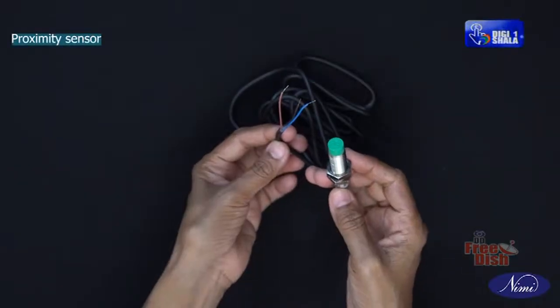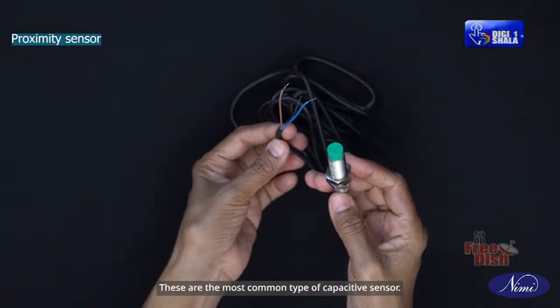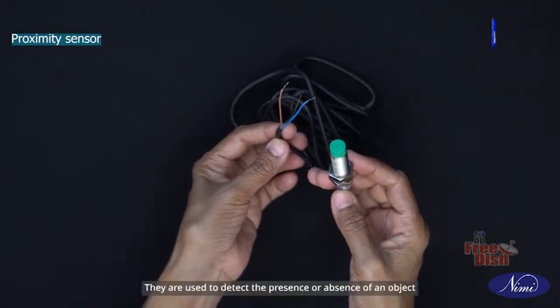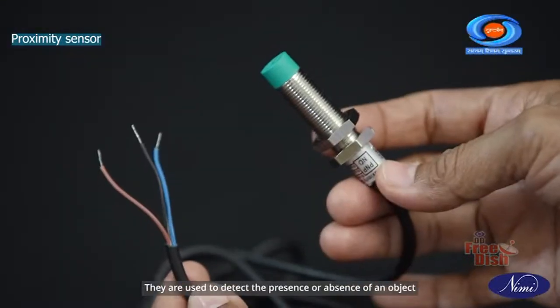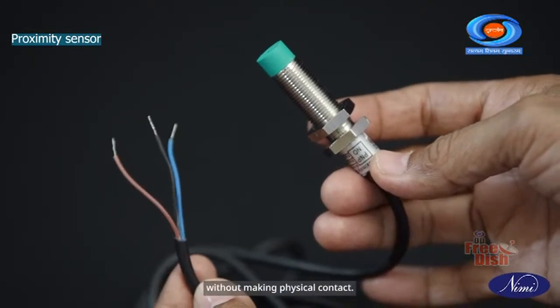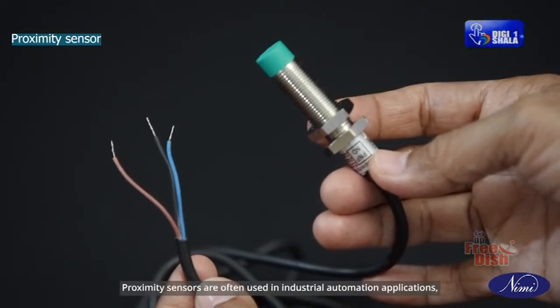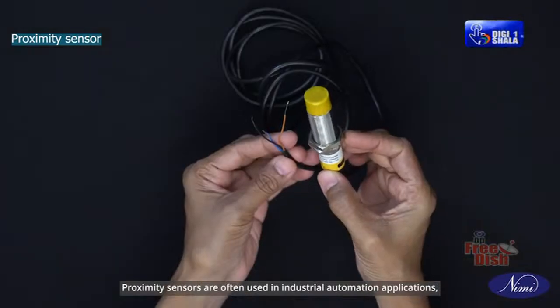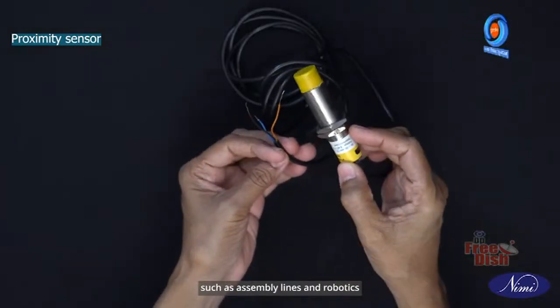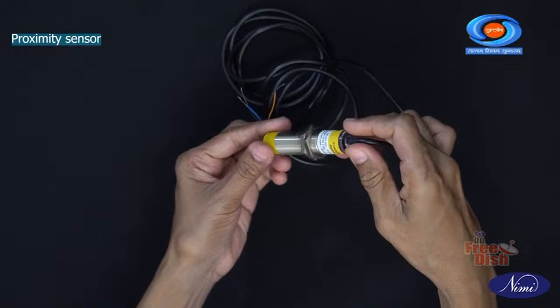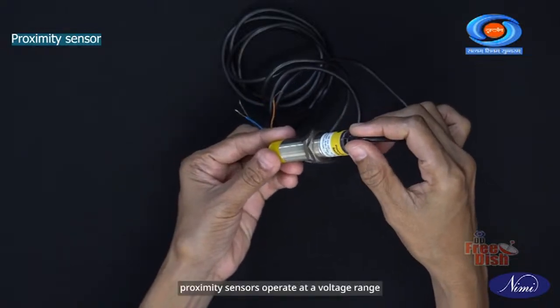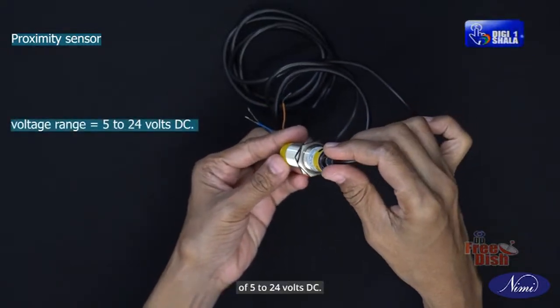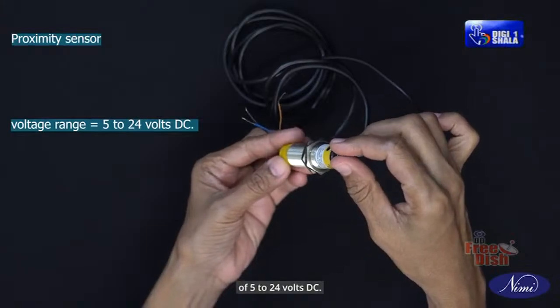Proximity sensors. These are the most common types of capacitive sensor. They are used to detect the presence or absence of an object without making physical contact. Proximity sensors are often used in industrial automation applications such as assembly lines and robotics. Typically, proximity sensors operate at a voltage range of 5 to 24 volts DC.